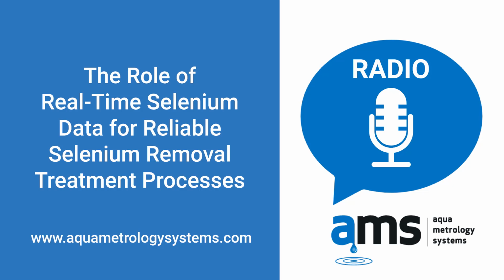Well, what are the challenges of monitoring selenium? So selenium is a very difficult chemical to analyze. The principal way that it's been done until now has been in the laboratory using standard approved EPA methods. The problem is that the application of those methods can actually result, if not done very carefully, in certain components of forms of selenium actually being destroyed, evaporating during the analytical process. And as a result, the amount of the selenium that's detected in the laboratory can be significantly understated.